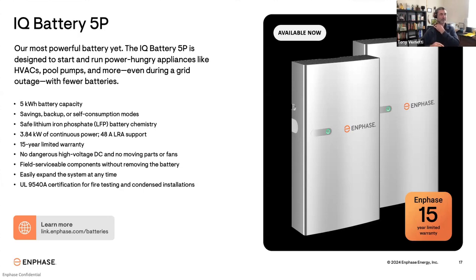Our batteries have a 15-year limited warranty. There's no dangerous high voltage direct current in our batteries. And just like with our individual microinverters, there are no moving parts or fans in the battery system either. It's designed to be much more field serviceable than our previous generation as well. So in the rare chance that there is an issue with the microinverter or even with one of the circuit boards inside the battery, it can be serviced on site without having to ship the battery back to Enphase.